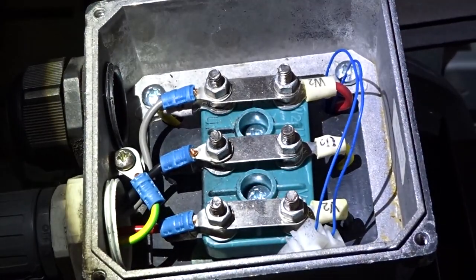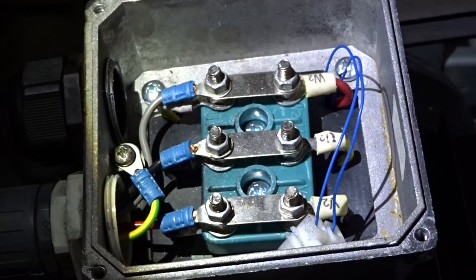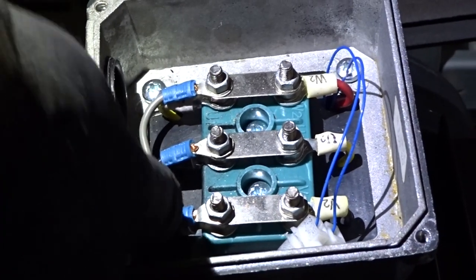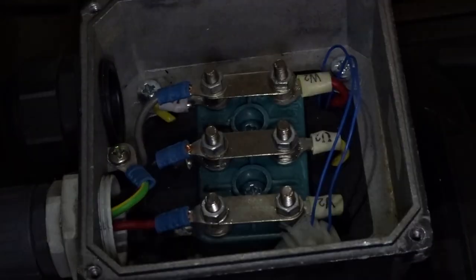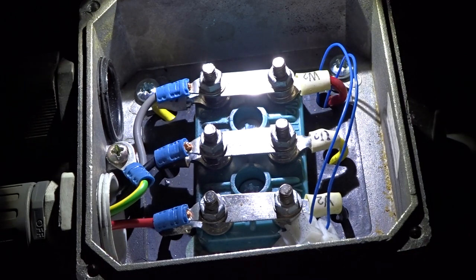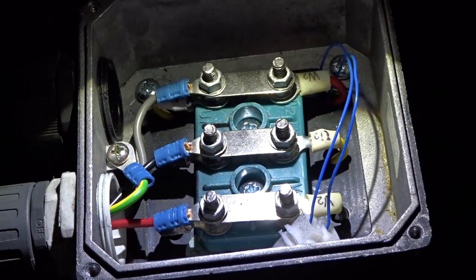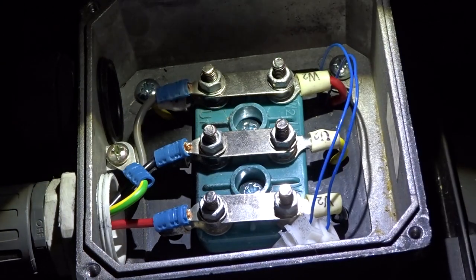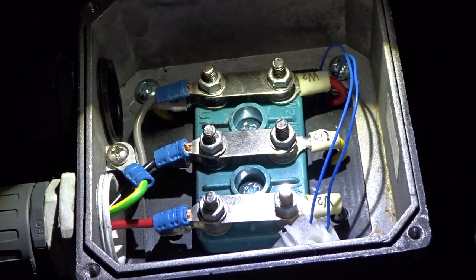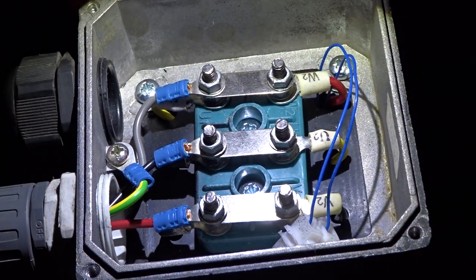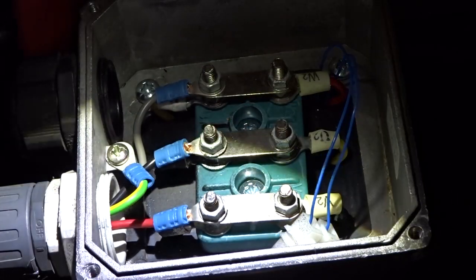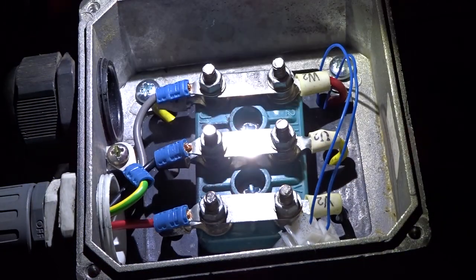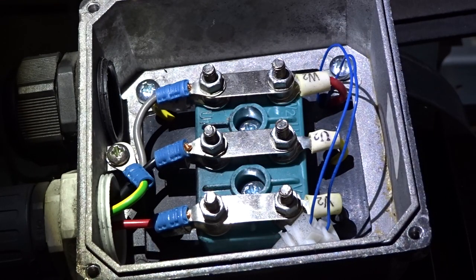These fans are running constantly, so vibration and wobble could cause the screws to come loose. So I'll just go around and check them all. Okay, that's complete. I'm just going to check, get inside with the torch and just check, give it a blow to remove any dust, check all the connections to make sure they're okay. I'm happy with that, that looks okay to me.